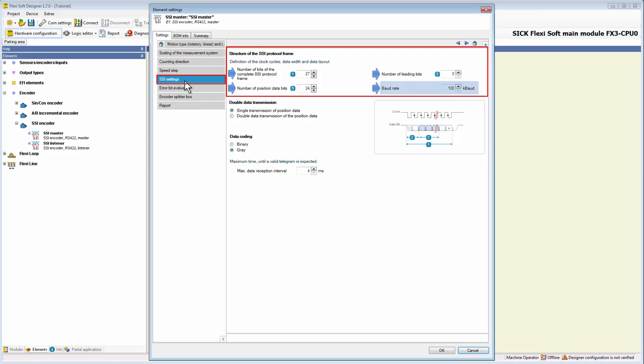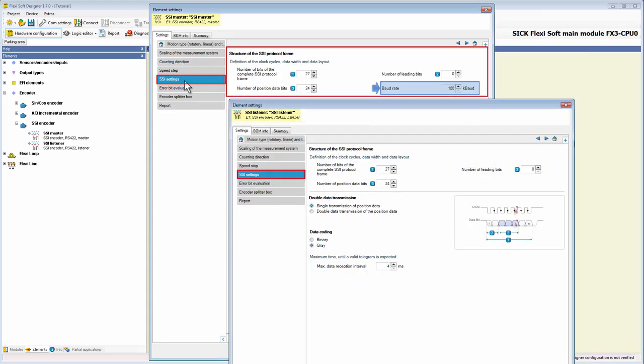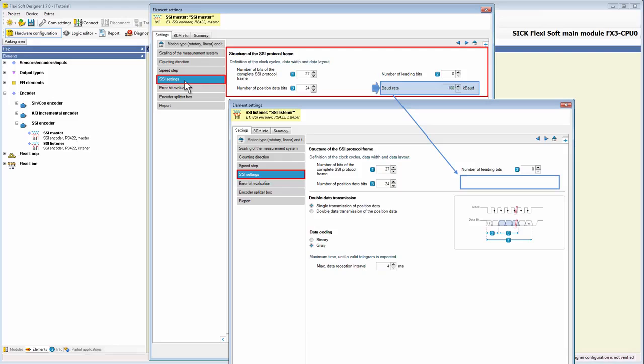At this point, it's important to mention that the parameter baud rate is only available at a SSI master. If we take a look at the tab SSI settings of a SSI listener, we notice that the parameter doesn't exist, because the value of the baud rate is defined by the SSI master and synchronized by the SSI listener.